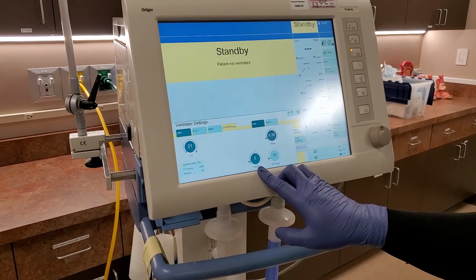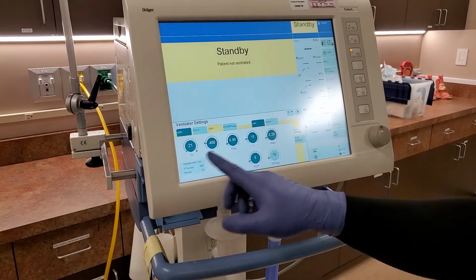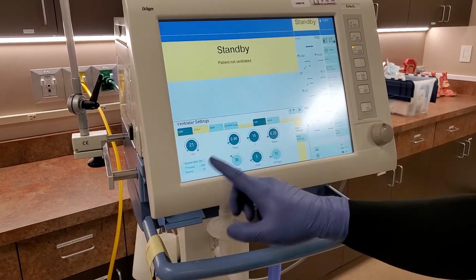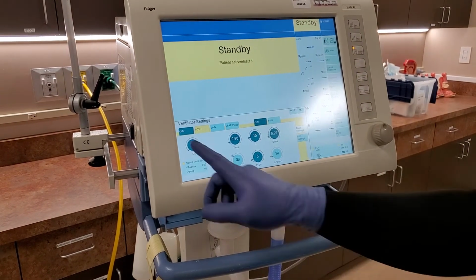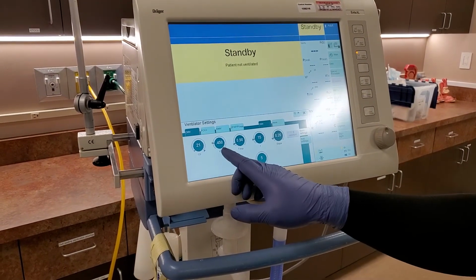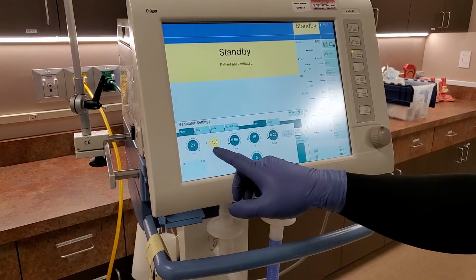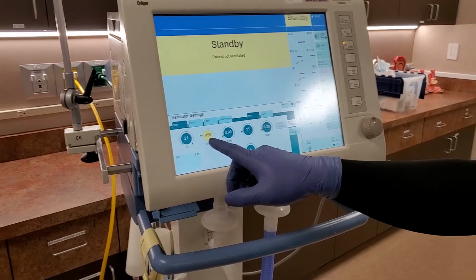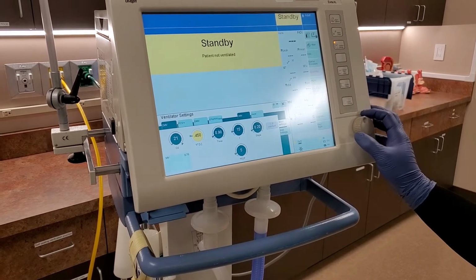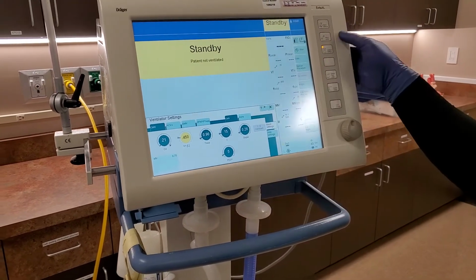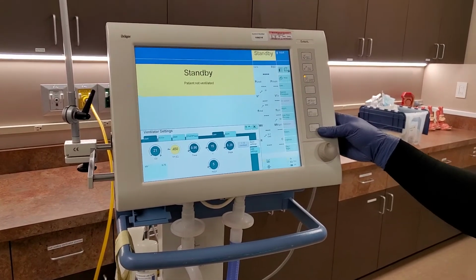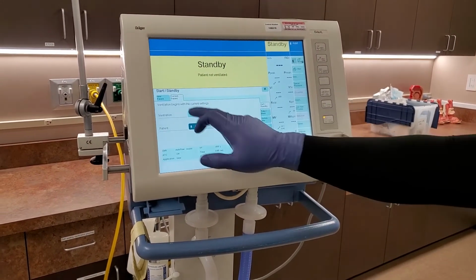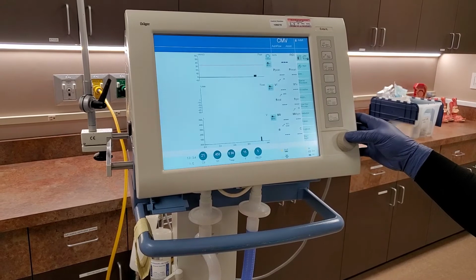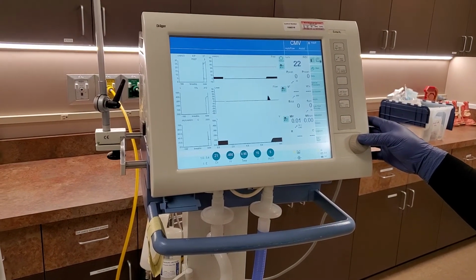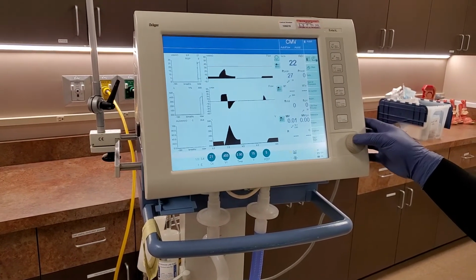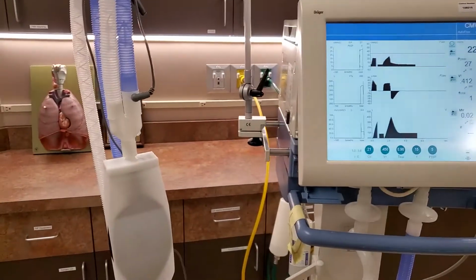So you just put the peak and the pressure supports. And then there's SIMV. And then there's SIMV PC, and then ACVC where you set tidal volume here. It's actually set in liters, so it's 0.450. So we'll select this, and then to start, you hit start here. And there we go. Then you can see the test lung inflating.